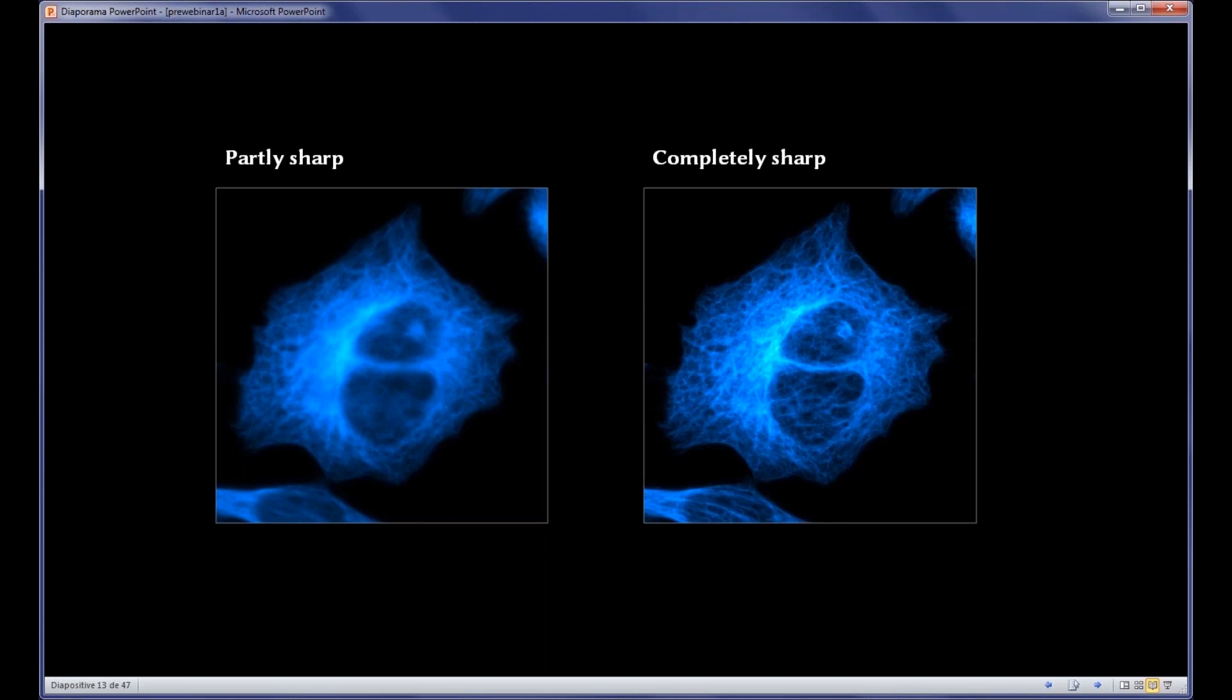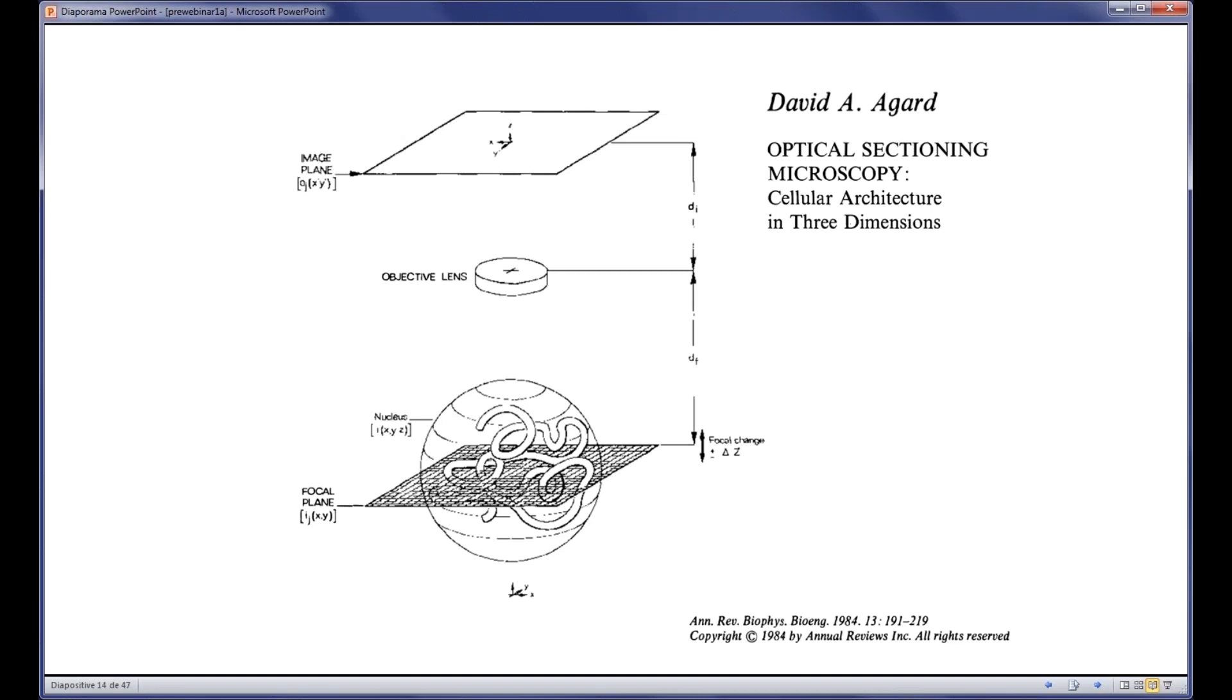The light is collected by the objective lens, gathered back and sent through the dichroic mirror, which filters it from the light source and then through emission filter, which filters the rest of the light source light and is detected by detector. In the present situation, the detector is not anymore the film, but in most of the cases, it's the camera. It is a very powerful approach, which is very efficient. The light is used very efficiently, but the problem is that the light from outside of the focal plane is mixed with the light from the focal plane. So the focused light is mixed with the non-focused one. And by the end of the day, the resulting picture is blurred. But in most of the application, especially for three-dimensional systems such as any nervous system, neurobiology model system, we want to be three-dimensional and completely sharp. So how are we going to achieve this? There is a very nice paper which is dedicated to optical sectioning microscopy.